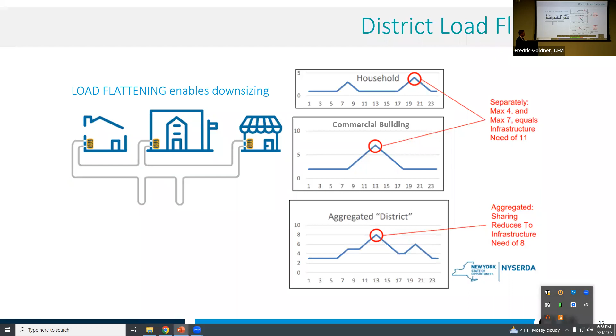The advantage of load flattening is that the primary heating and cooling source is the ground heat exchanger. This piping is high density polyethylene plastic—even 50 to 100 years is an underestimate; 300 years is literally what the manufacturer tells us it's good for. It absorbs heat at no additional cost, absorbs pressure, expands and contracts through the seasons, and is uninsulated, allowing low-grade heat recovery opportunities—meaning I can scavenge heat from many different sources and blend it into my loop, or sink heat in many different ways by blending it back out.